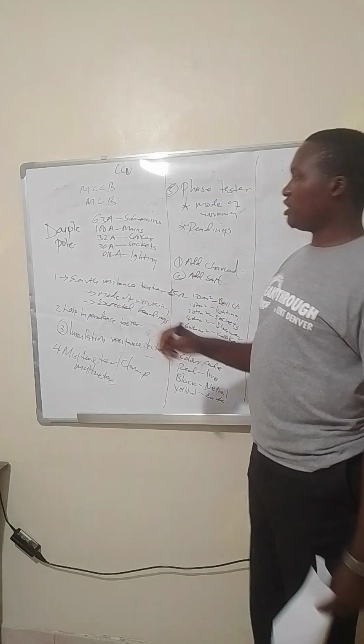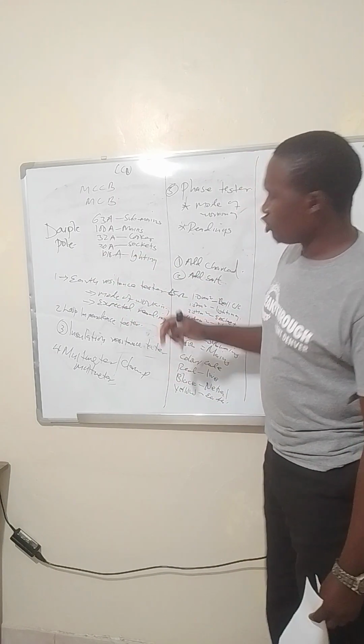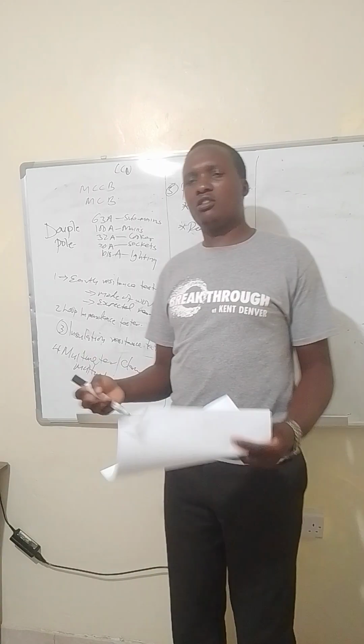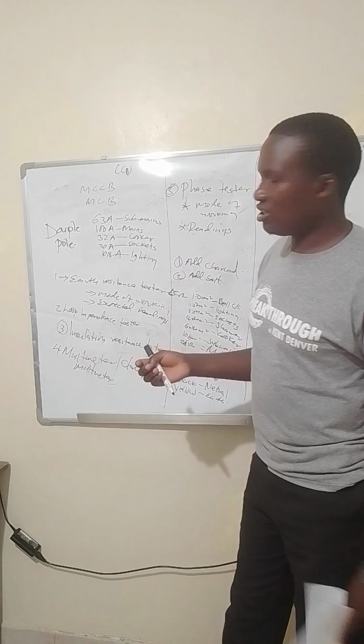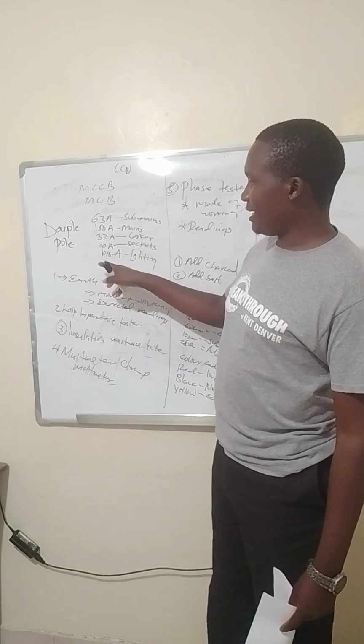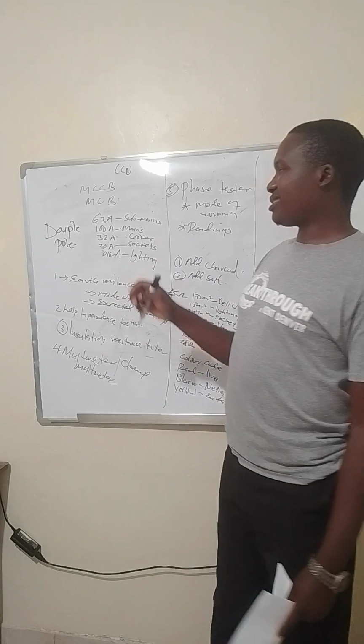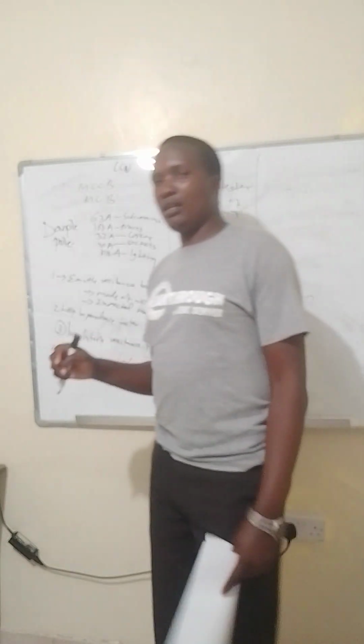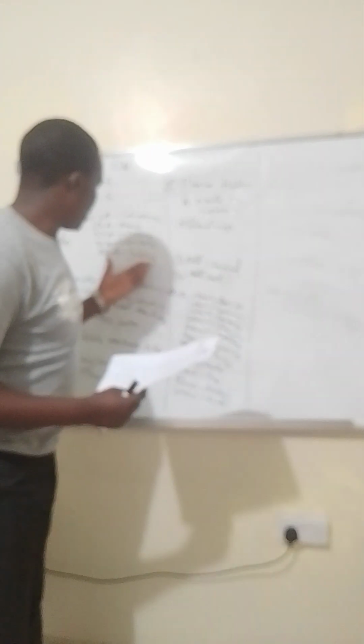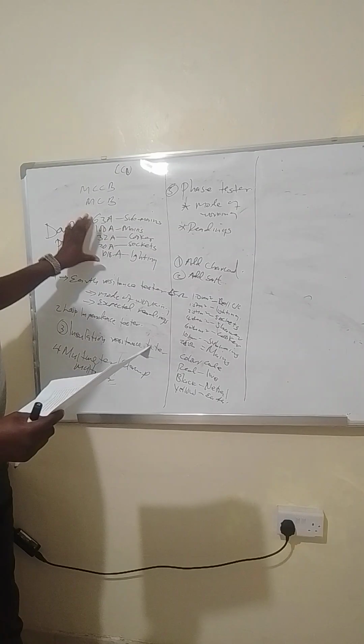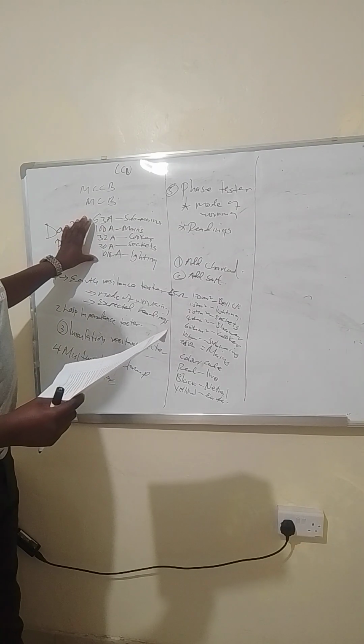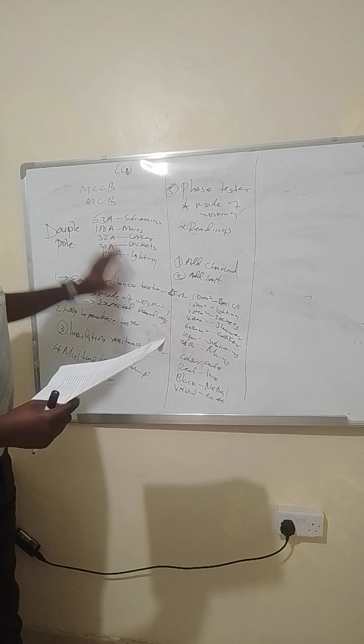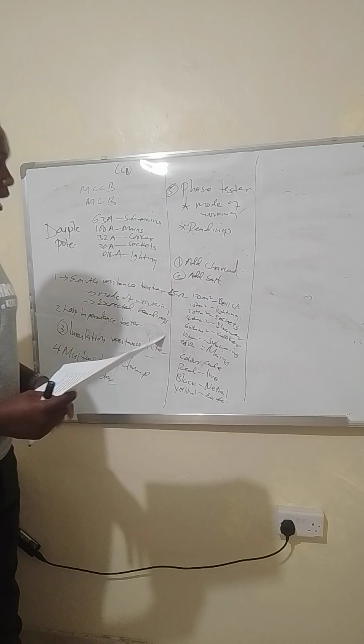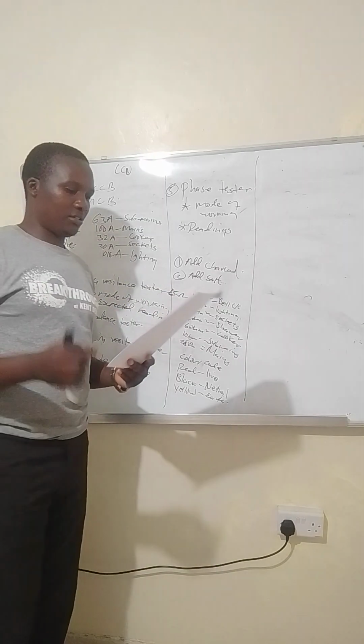20 amps is used in sockets, because with sockets we don't have too many appliances, so we use 20. 10 amperes we use in lighting circuits. So you need to be very careful when answering. Mostly the questions on protective devices and cables go hand in hand, so be careful when selecting those answers.